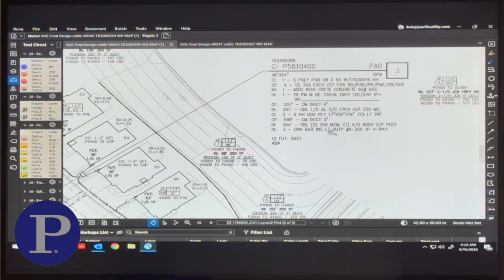And then if we go back to that description of the transformer pad, we know that this is the transformer number. We know that this is the description right here of the transformer. 75 kVA, 16 kV. What this is also going to tell us is that you had 207 feet of primary cable coming to that transformer, and it's also going to tell us that we have 344 feet of secondary cable. So secondary is going to be what feeds out of the transformer to the secondary handholds that's in turn going to feed into the service panels.